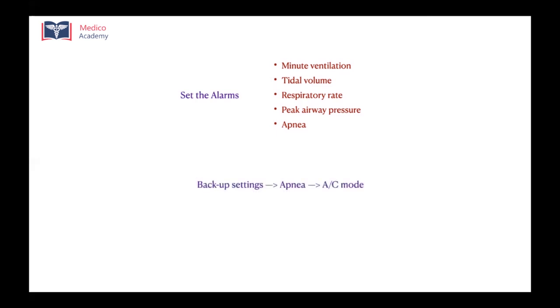Like when the patient goes into apnea, the ventilator will have a backup setting, which will be some kind of an assist control mode, either a pressure assist control mode or a volume assist control mode, where you can set the tidal volume and respiratory rate. Suppose the patient goes into apnea, then you are instructing the ventilator to deliver tidal volumes to the patient at a fixed rate, so that the patient doesn't die of respiratory failure. So that's a safety mode.